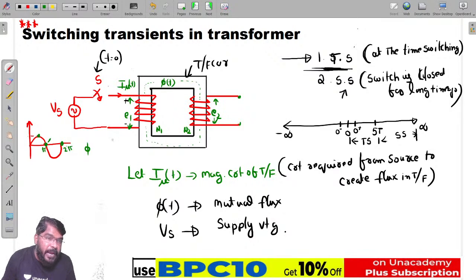That's why practically the switch is closed in between these points, the minimum value and maximum value. We cannot close the switch exactly at the maximum value in practical cases, but the severity of the transients is less if the switch is closed at the instant of maximum value of supply voltage. The severity of the transients is more if the switch is closed at the instant the supply voltage crosses the zero crossing point.